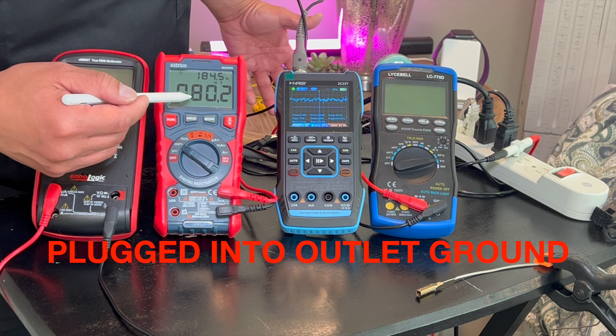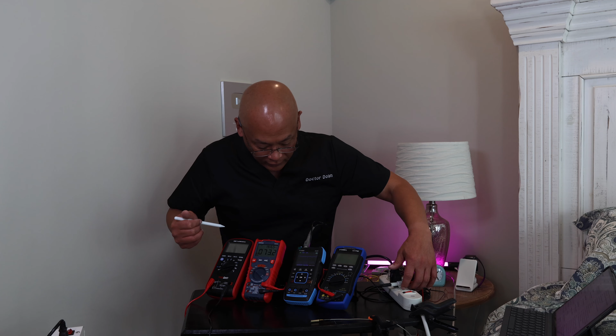So let me show you what happens with an outlet ground versus an earth ground or a grounding rod outside. Here's the waveform with a peak to peak of about 1 volt, and also about 79 to 80 millivolts of alternating current in the ground wire. This is from the outlet. Zero stray voltage here, and this is flatline.